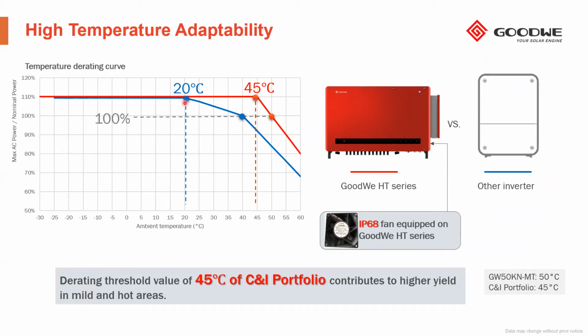The derating, that I guess everybody knows, is the firmware, the algorithm that the inverter uses, or that we introduce in the inverter, we design this way to control the input power and therefore the heat inside of the inverter, to avoid precisely overheating inside of the inverter. The most critical element in an inverter is the IGBTs, the transistor. Isolated gate bipolar transistor is the acronym of IGBT, and it's very sensitive to high temperature.